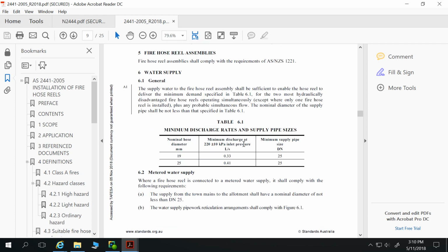Okay, so we've already determined that we need fire isolated stairways and we need 2 of them because of our distances. We need to have a hydrant on every level. We've determined that. And we've also determined that wherever we have a fire hydrant, we need to have fire hose reels. Right? So we've got to have a hydrant and at least 1 reel on every floor. By that, we might need extra reels if that 36 metres isn't going to be enough to put out a fire at the other end of the building. So it begs the question, do we need to put in another fire hydrant?